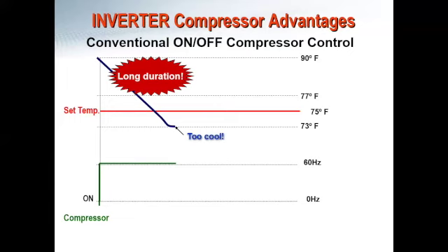But when you're trying to get to that 75 degree set point, your conventional compressor is going to kick on to full power, 60 hertz, and draw all of that energy in to start cooling that space as quickly as possible. Unfortunately, because you have such a long way to drop that temperature, it's going to take a long time to bring down from 90 degrees all the way to that 73 degree set point, or actually 2 degrees below the deadband where it's going to try to go. Once it does hit that 72 or 73 degree set point, your compressor is actually going to turn off. That's traditional compressor technology. That's how it's always worked in HVAC systems for time immemorial. So once you reach the 77 degree deadband, which is coming up over that 75, you're going to kick back on.